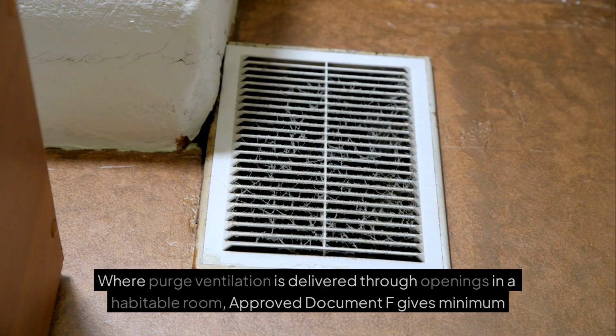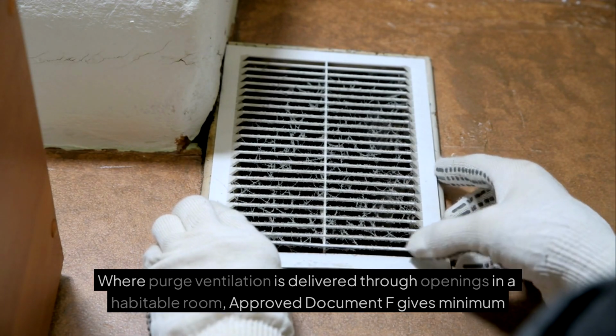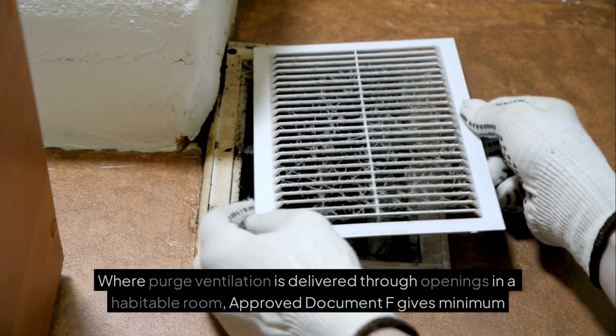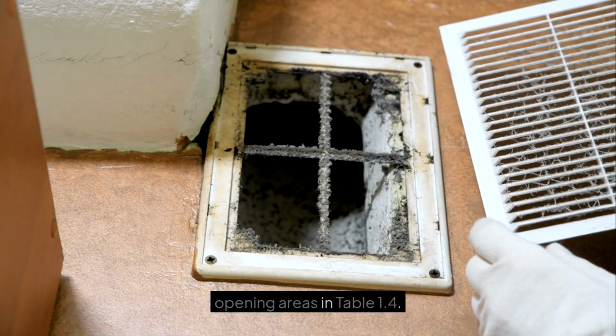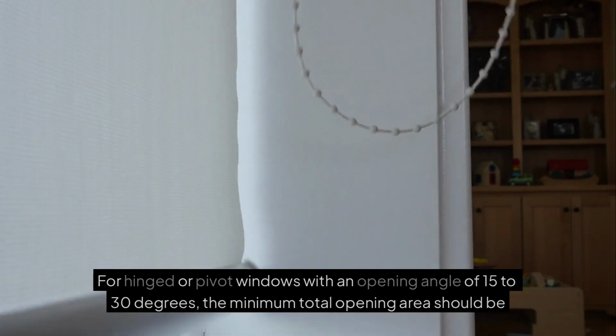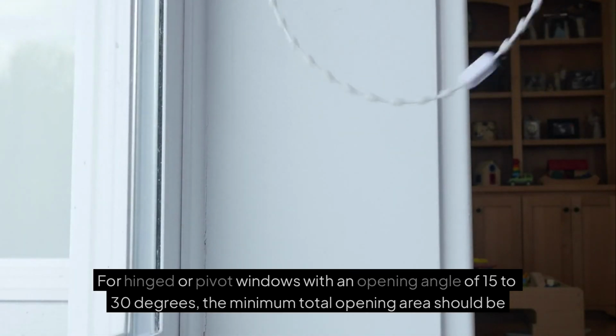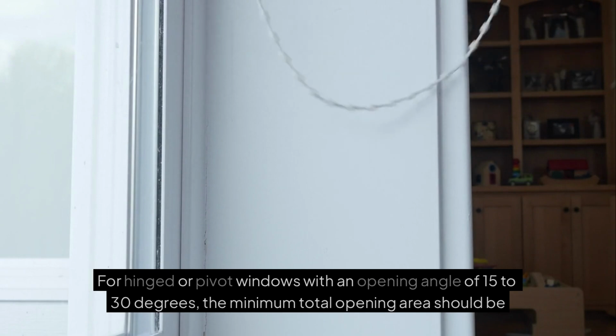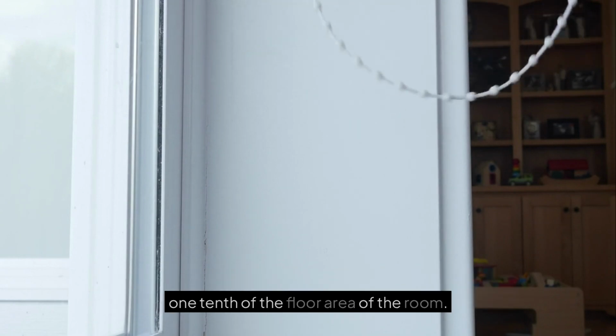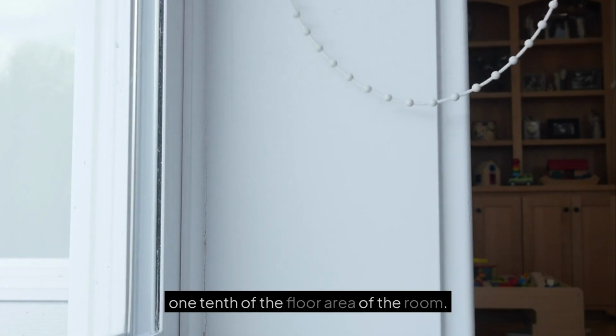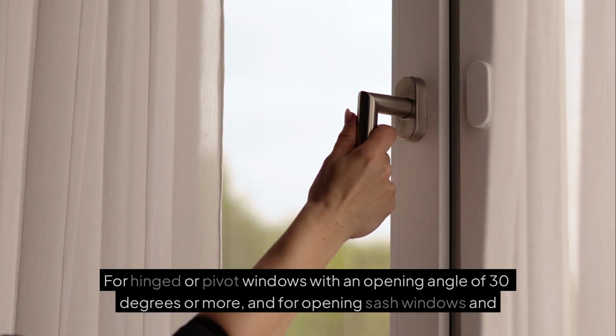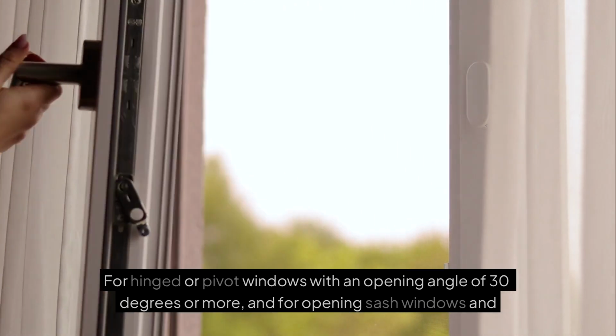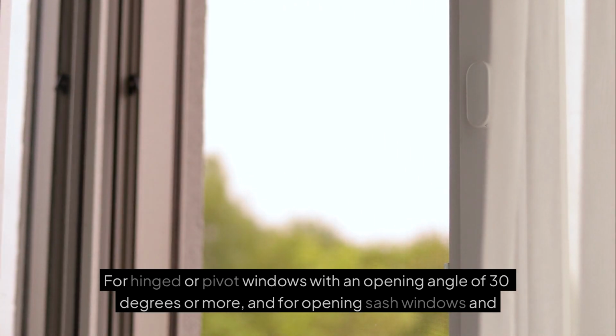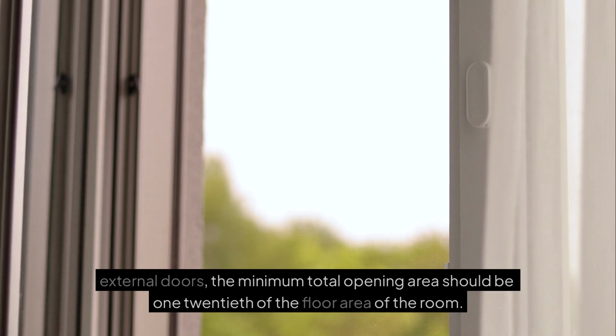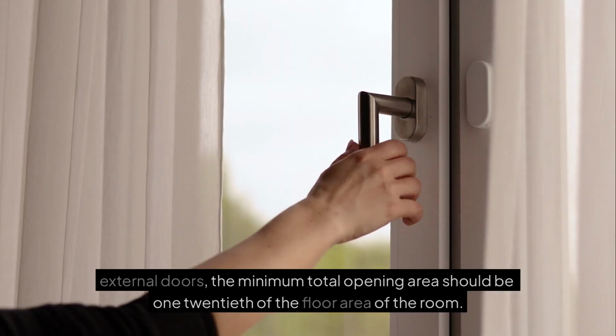Where purge ventilation is delivered through openings in a habitable room, Approved Document F gives minimum opening areas in Table 1.4. For hinged or pivot windows with an opening angle of 15 to 30 degrees, the minimum total opening area should be 1/10 of the floor area of the room. For hinged or pivot windows with an opening angle of 30 degrees or more, and for opening sash windows and external doors, the minimum total opening area should be 1/20 of the floor area of the room.